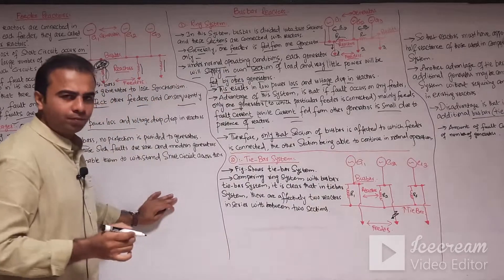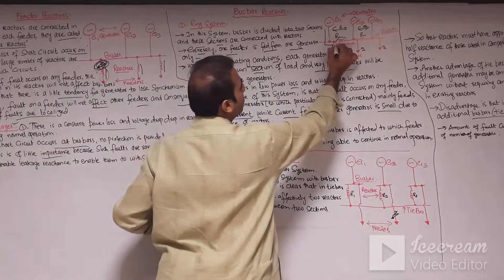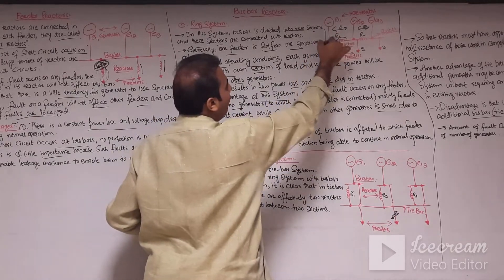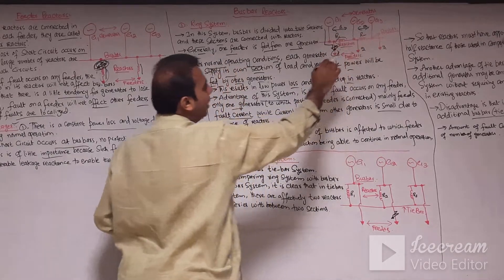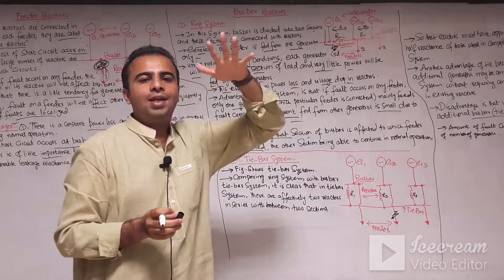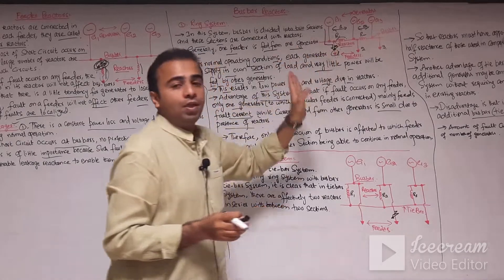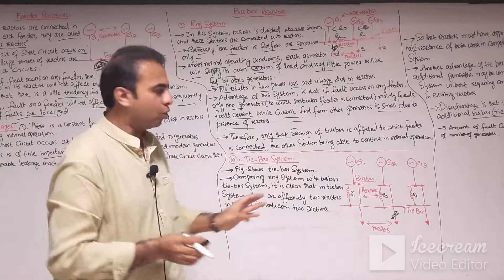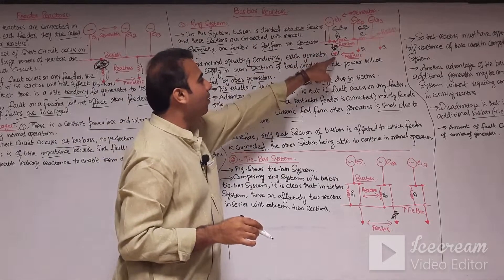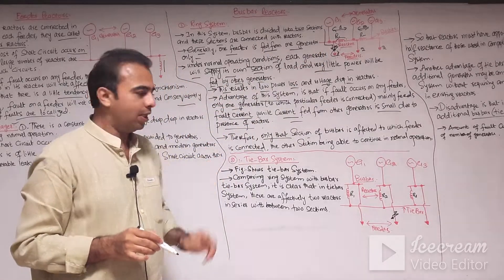Therefore, only that section of the bus bar which the faulty feeder is connected to is affected, while other sections continue their normal operation. If a fault occurs on feeder 1, G1 generator is affected while G2 and G3 continue running under normal operating conditions, because the reactors provide additional reactance to limit the short circuit current on the G1 side.